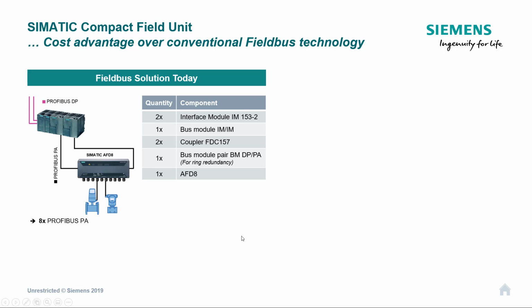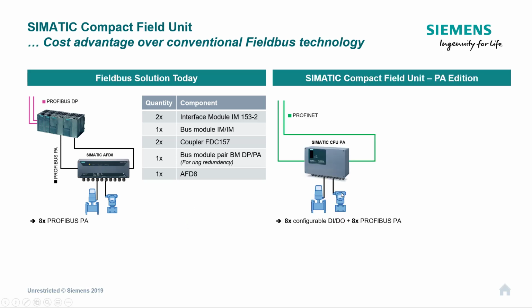So if we have a look at the components, there's more components there, there's more wiring, there's more time, and of course, as I keep saying, you've got the cabinet that you have to build to house these Profibus DP to PA converters. So if we look at the Compact Field Unit, it supports media redundancy, so that's on the Profinet side.